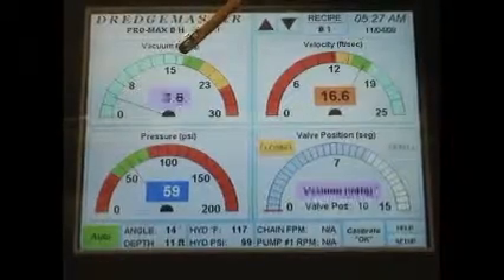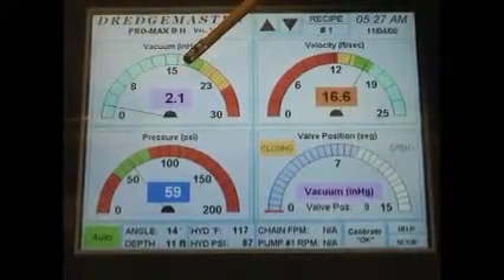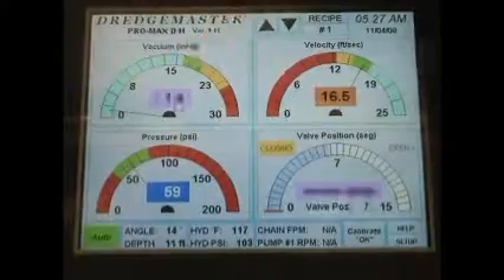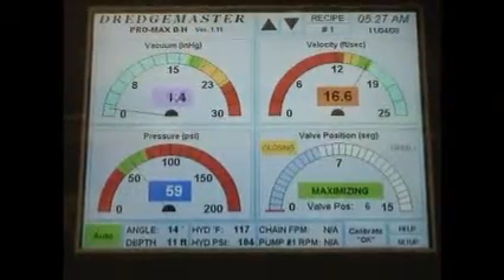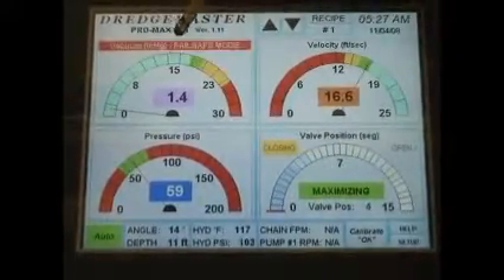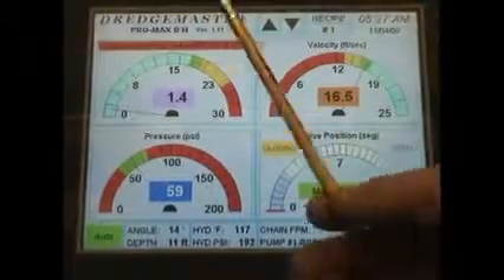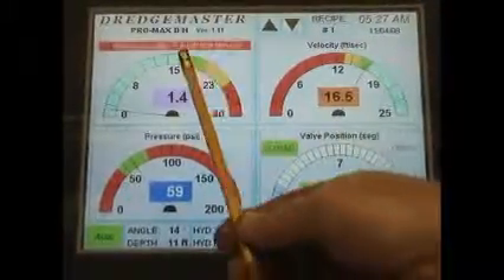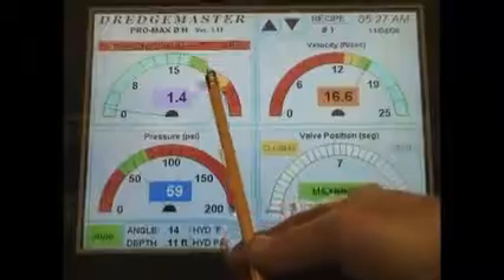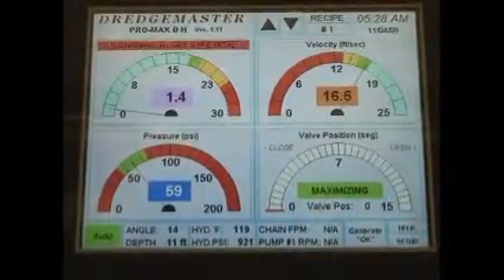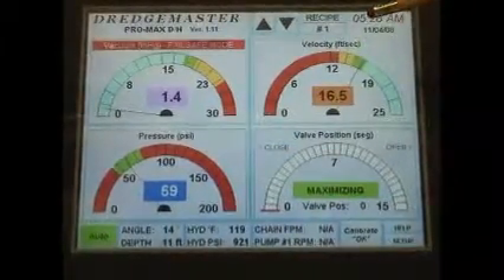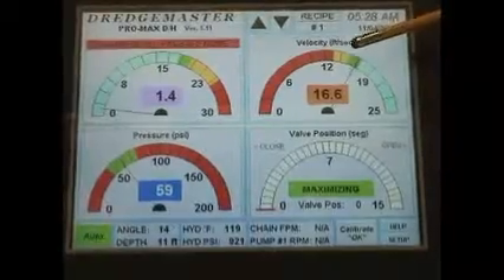Once we're dropped below 2, give it about 5 seconds. Now our vacuum fail-safe mode has kicked in, which has reduced our green area here. It's going to open up the valve just a little bit quicker than what it did before. But our valve will continue to operate off of velocity and pressure.